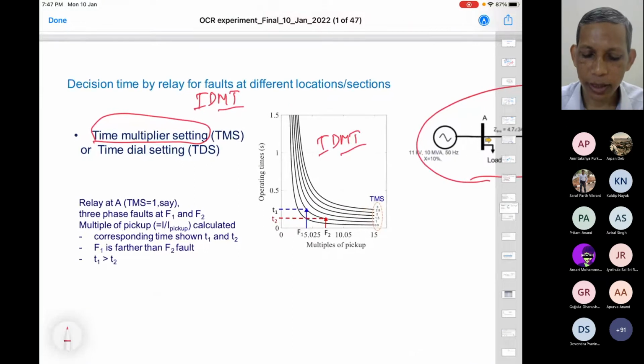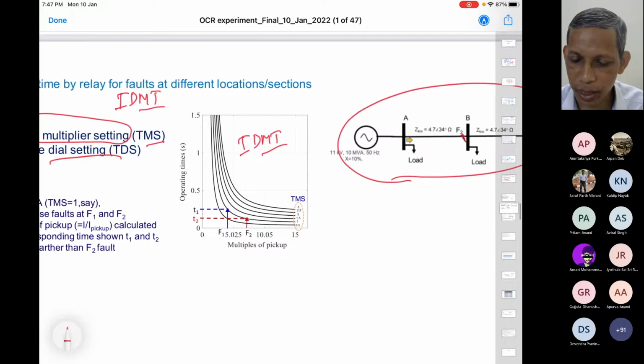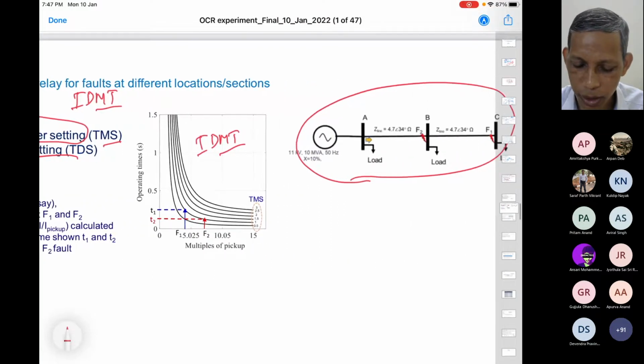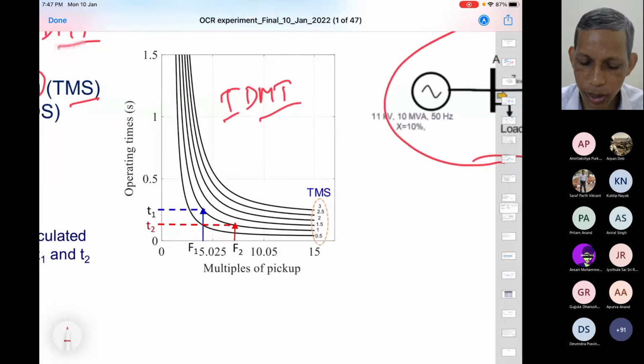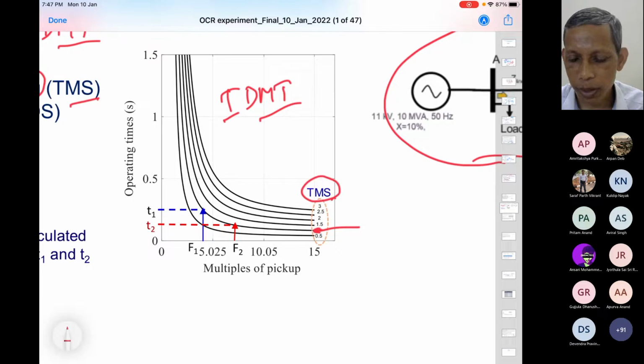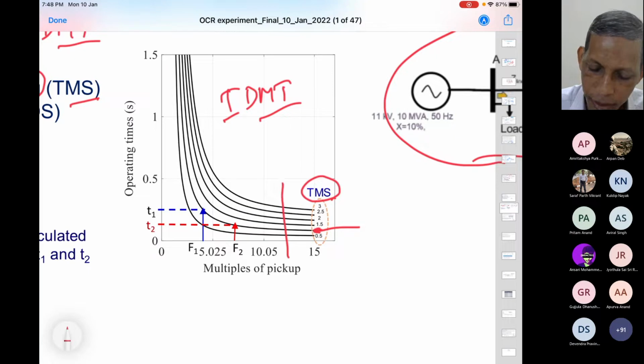So time multiplier setting, TMS, or time dial setting, is time control. What is the time control? Suppose this is any curve, say moderately inverse, an IEEE curve. So this is 1, I'm marking it 1. If I multiply with 0.5, it will be lower. If I multiply with 3, it will be larger. So TMS is a factor. If I multiply that factor, then the corresponding decision time at any instant changes.